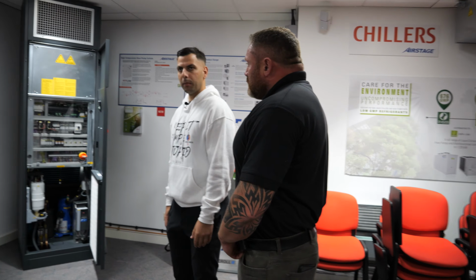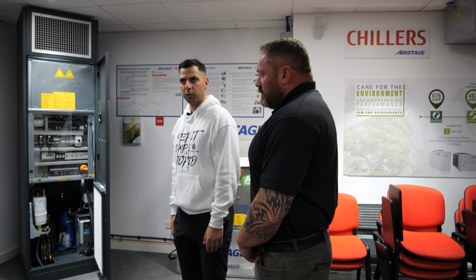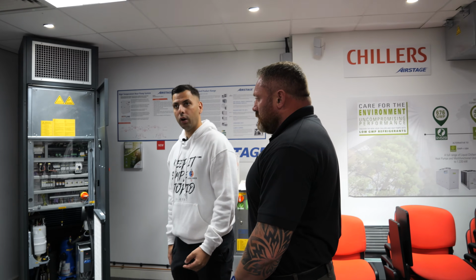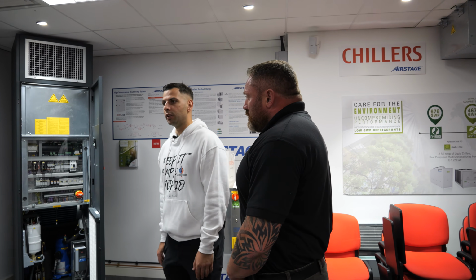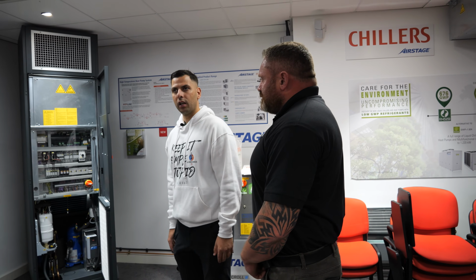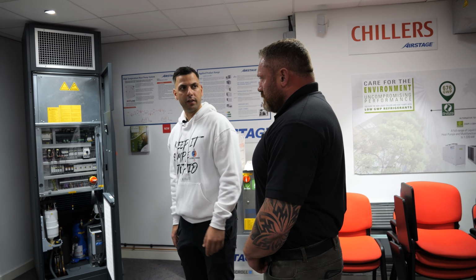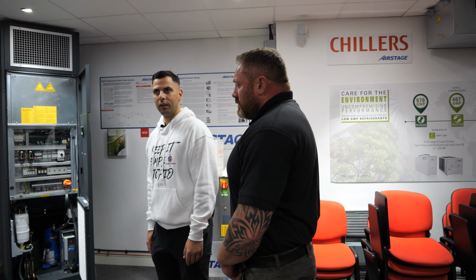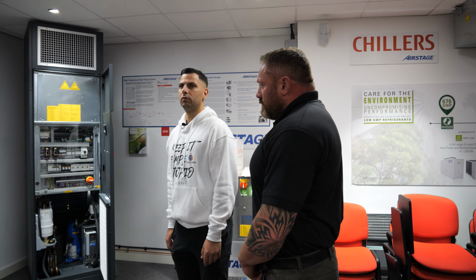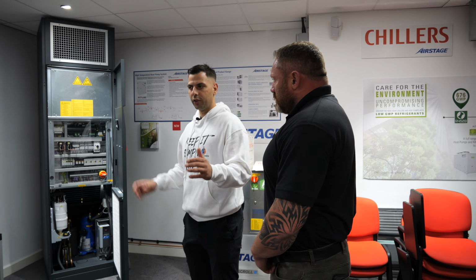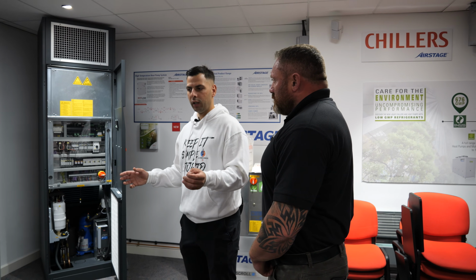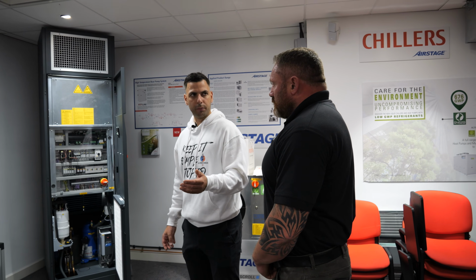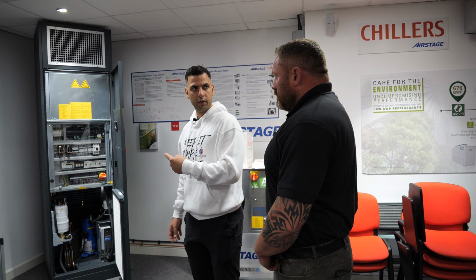Dean, the amount of AHUs that we're involved with and quoting work-wise, it's a no-brainer, because the question is always there about what you're doing with preheat. Can you get us a 200 amp supply to do 3-phase preheaters? No, there's no power. But you would obviously get an AHU design - if we need 10 kilowatts of preheat, we'd just use your unit.